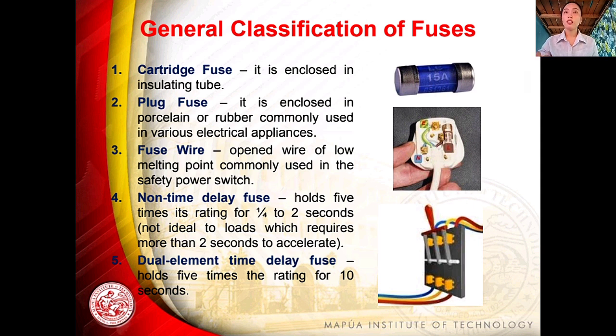And non-time delay fuse holds 5 times its rating for 1/4 to 2 seconds or not ideal to loads which require more than 2 seconds to accelerate. And dual element time delay fuse holds 5 times the rating for 10 seconds.